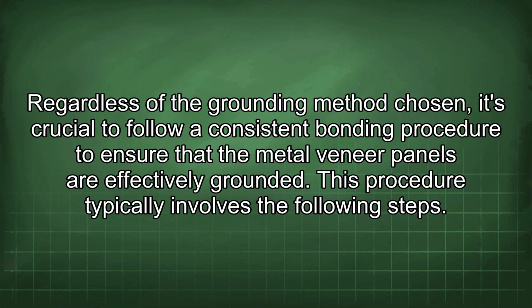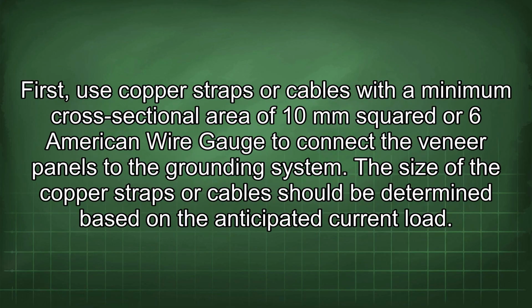Regardless of the grounding method chosen, it's crucial to follow a consistent bonding procedure to ensure that the metal veneer panels are effectively grounded. This procedure typically involves the following steps. First, use copper straps or cables with a minimum cross-sectional area of 10 mm² or 6 American wire gauge to connect the veneer panels to the grounding system. The size of the copper straps or cables should be determined based on the anticipated current load.